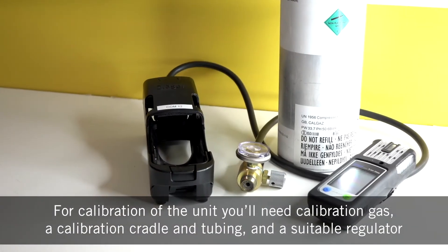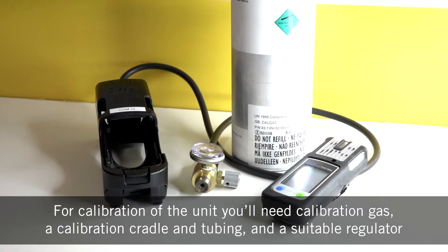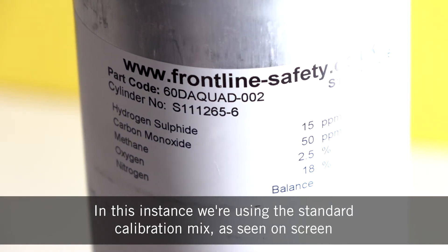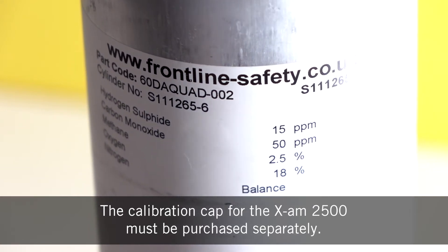For calibration of the unit you'll need calibration gas, a calibration cradle and tubing, and a suitable regulator. In this instance we're using the standard calibration mix as seen on screen. The calibration cap for the X-am 2500 must be purchased separately.